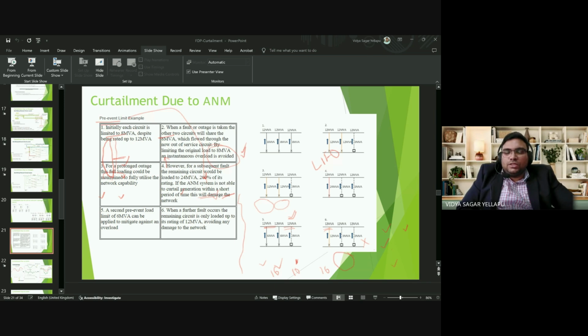the next one, which is the n minus one and n minus two situation. That means there are three assets here, each rated at 12 MVA, and the ANM system acts in such a manner that in the case of outage in any of these lines, the rest of the assets should not get overloaded, because each is rated at 12 MVA. In the steady state before any fault, which is called the pre-fault scenario, in the pre-fault scenario itself, it adjusts the generation of all the generators such that these assets are not overloaded.